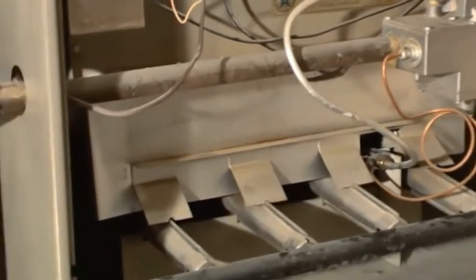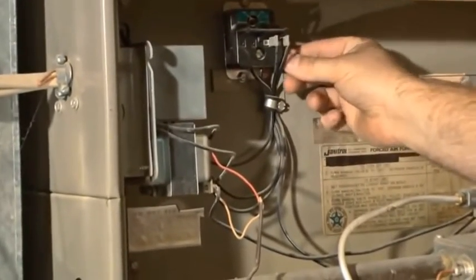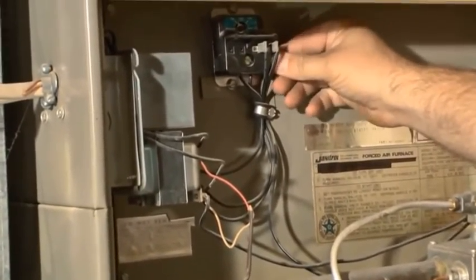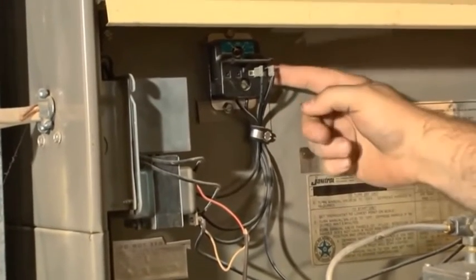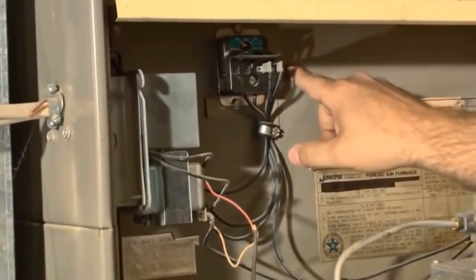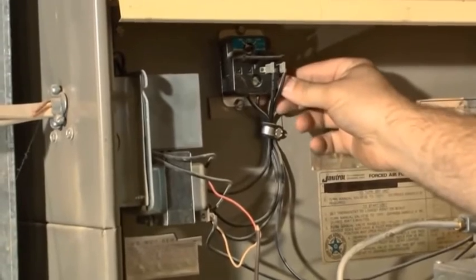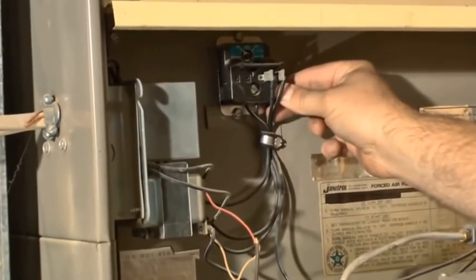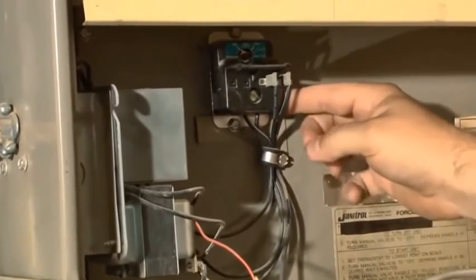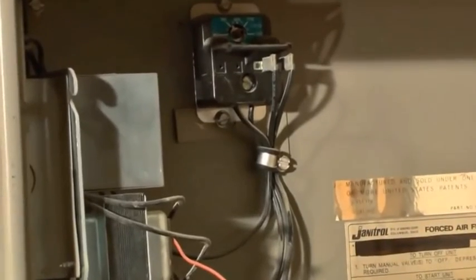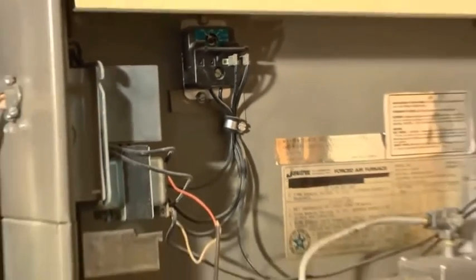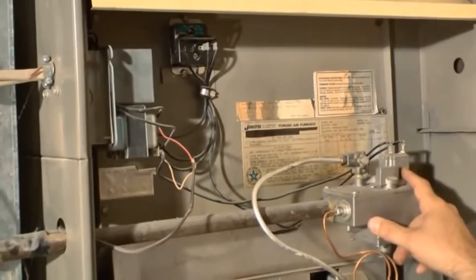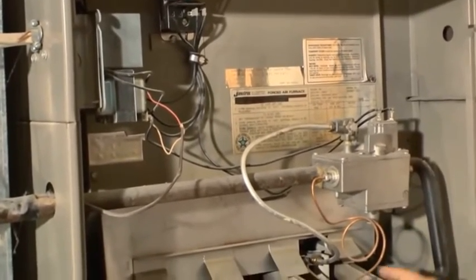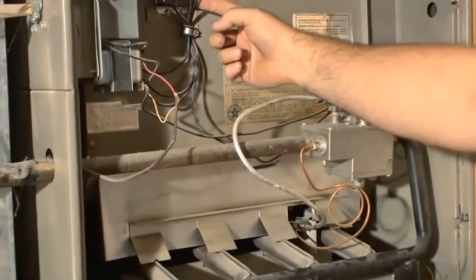Up here we have our fan control and our high limit. This has a probe that goes into the heat exchanger. If this gets too hot, it will actually break the power to the gas valve so that the gas shuts off and cannot continue to burn. So it has a safety built into it.